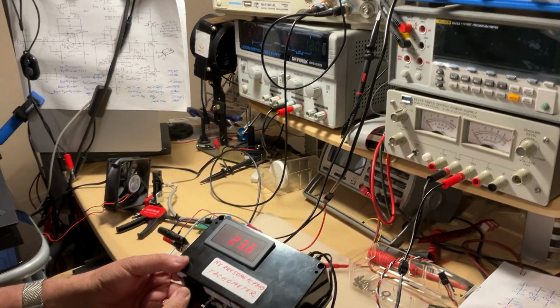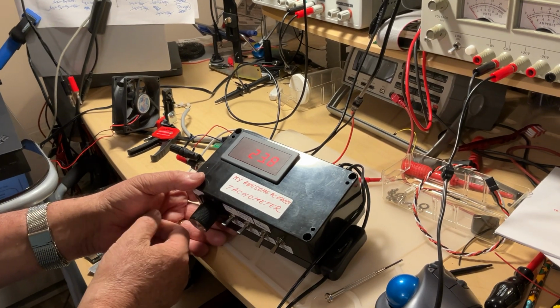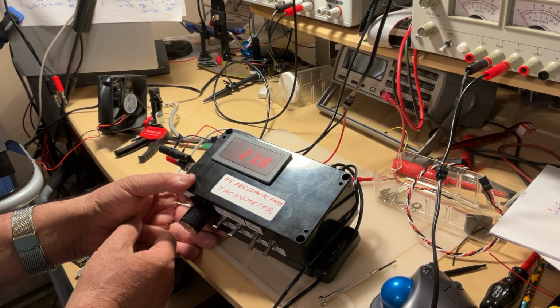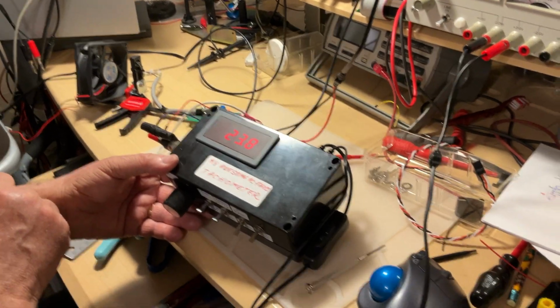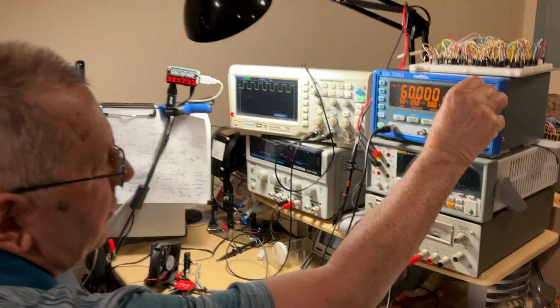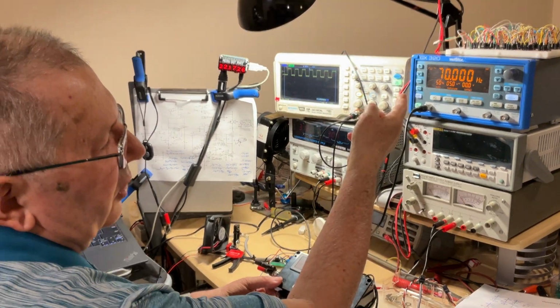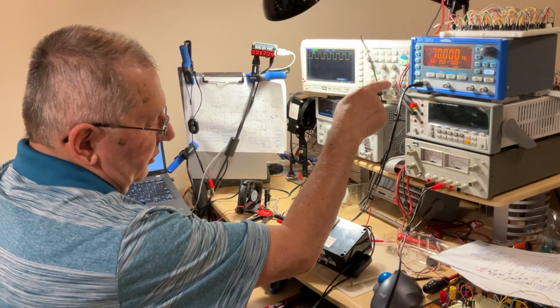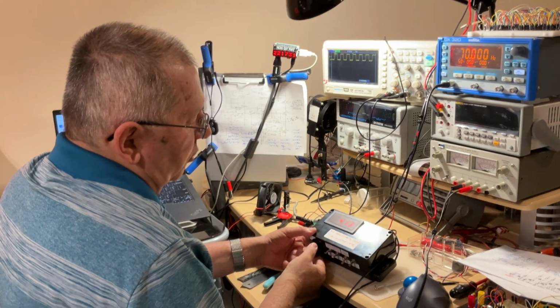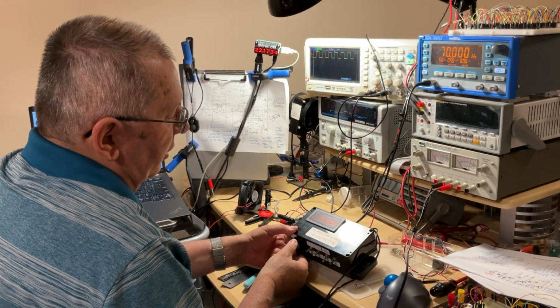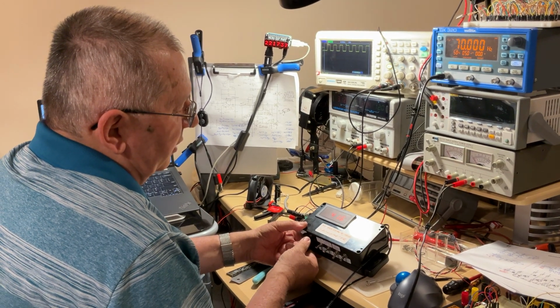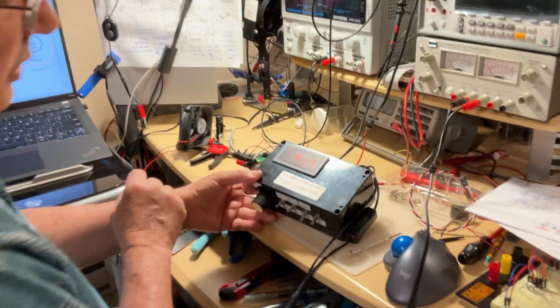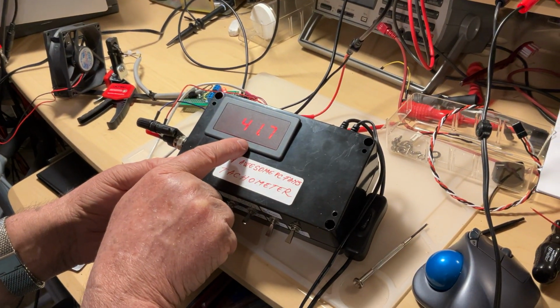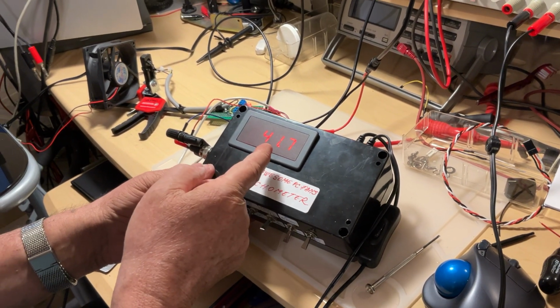For instance, I can move to another range like this one, and it's coming very close to 2400. If I put it to 70 hertz, 70 hertz times 60 is 4200. So the RPM, depending on what range I'm in, can go up to 4200. I still have to play a bit with the calibration to bring it exactly to 4200 - it's not far, but I'm just saying.